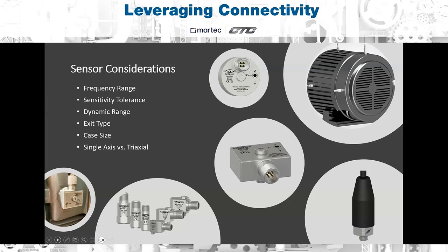Dynamic range refers to the maximum and minimum amplitude that the accelerometer can measure. The typical dynamic range of a CTC sensor is plus or minus 80 Gs. Exit type is another consideration you should have, whether that be a top or side exit. And I'll show a few examples of that in the next slide. Exit type also kind of goes hand in hand with case size. Typically, these decisions are based on clearance limitations of the mounting location. And I'll show you the different sizes that we offer for both top and side exit sensors.